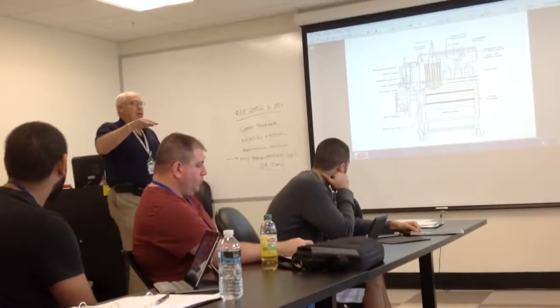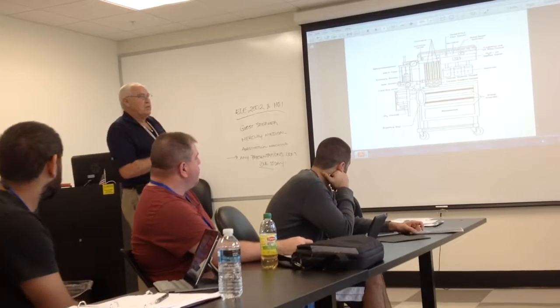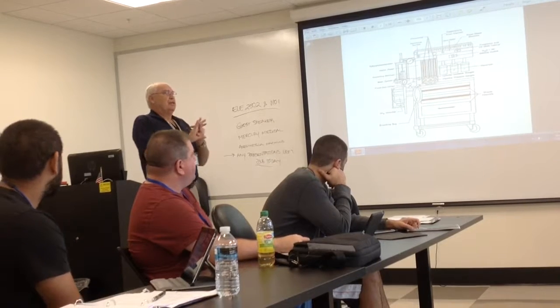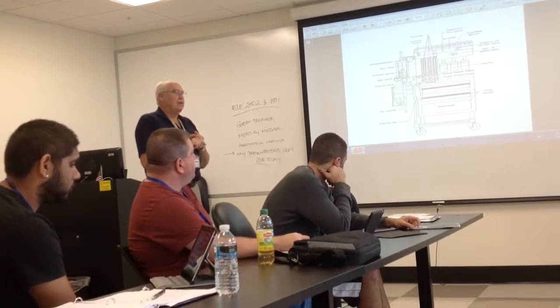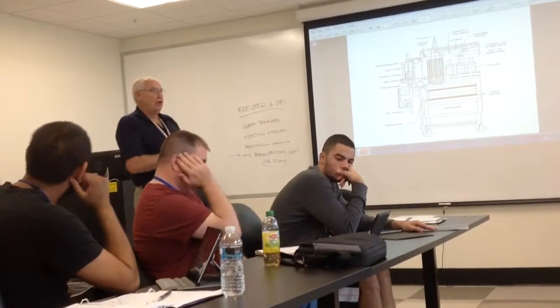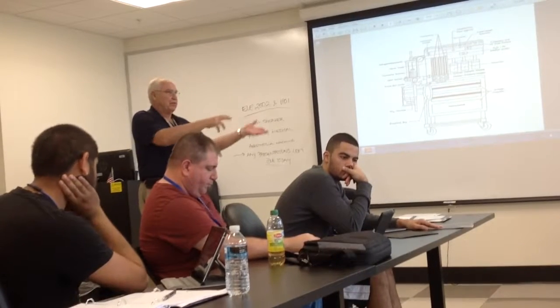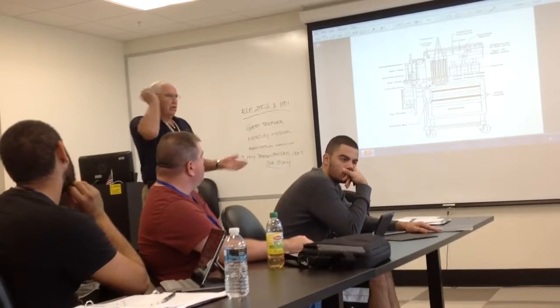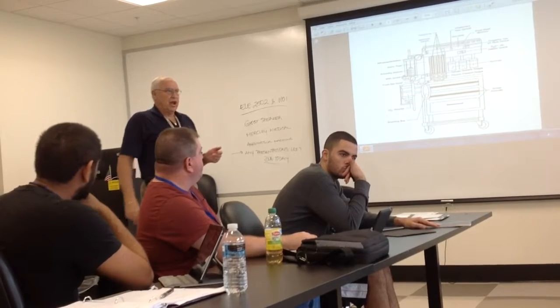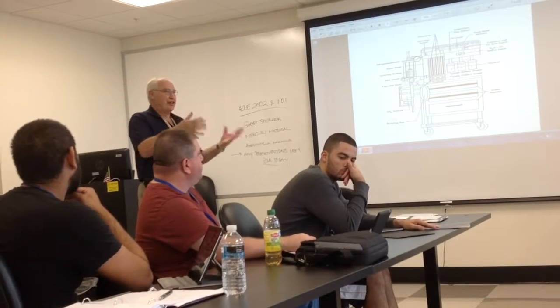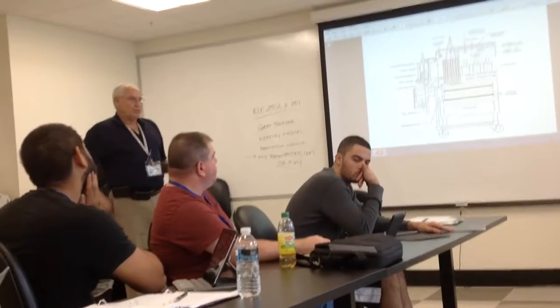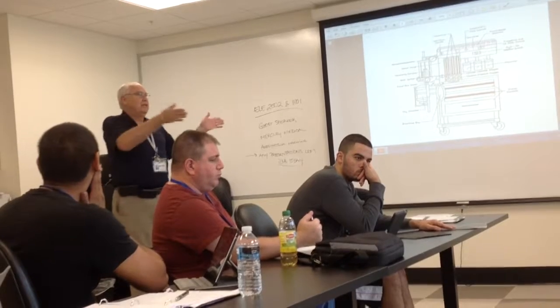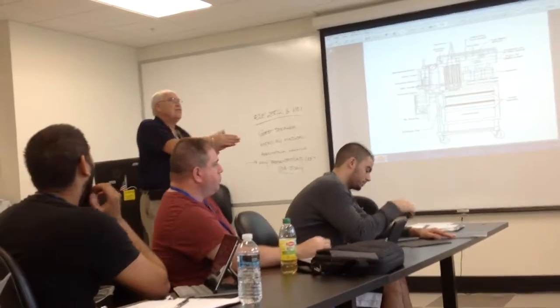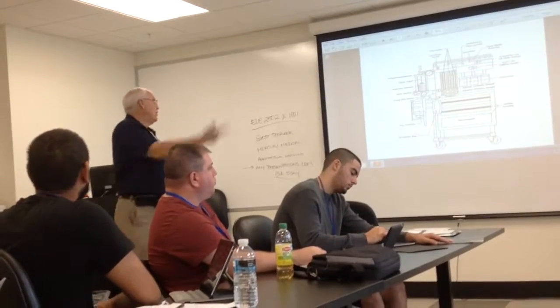As we have gone into getting more reliable equipment, people that are trained will be able to determine that a piece of equipment is starting to fail. That is the most important thing that you could do. Seeing a device that when you calibrate it here, 4 months later it comes back to the shop. Oh, it drifted. Why did it drift? How come it's not holding its calibration? That's where you are going to grow in this business. When you're able to determine those and make these devices that much more reliable. Okay?